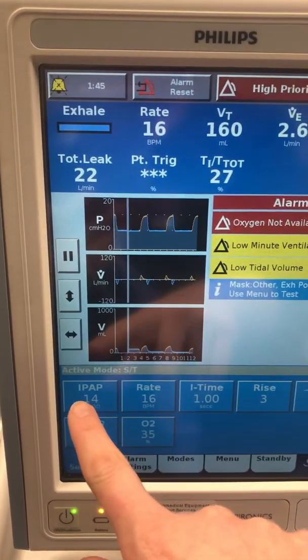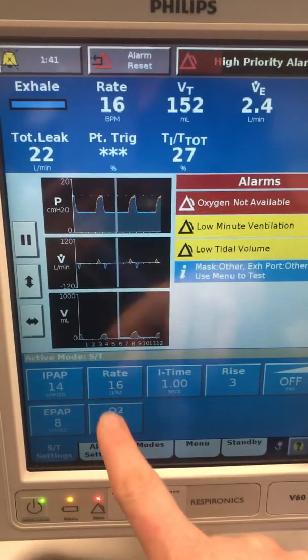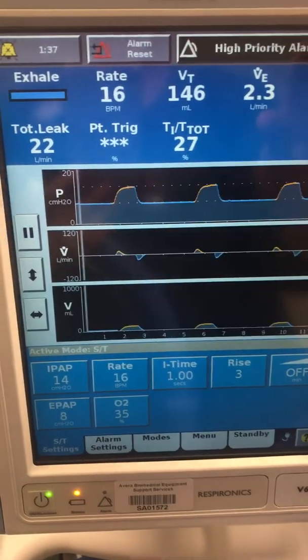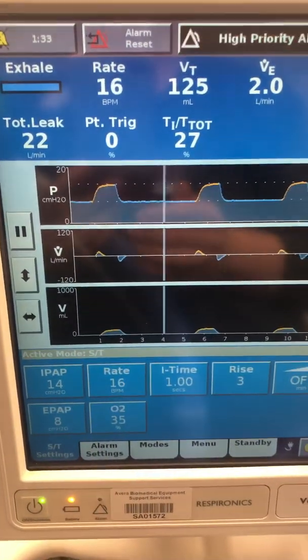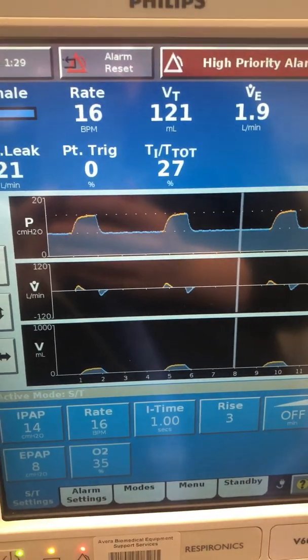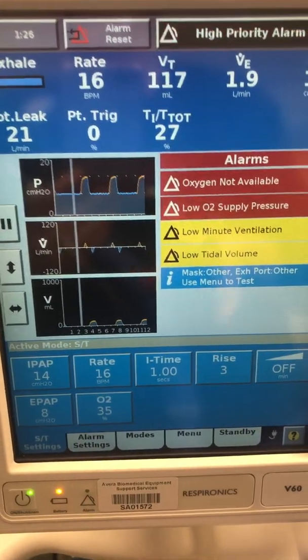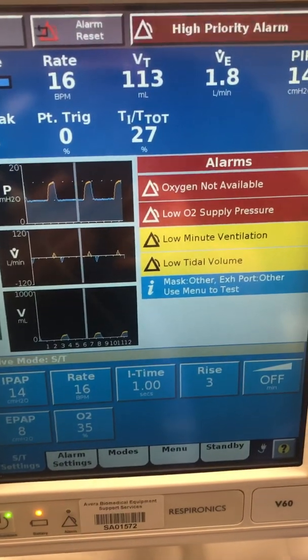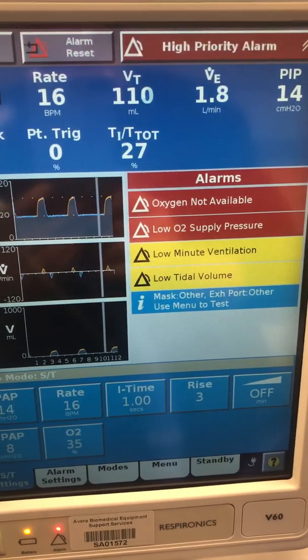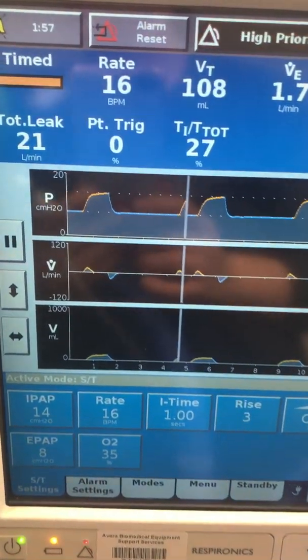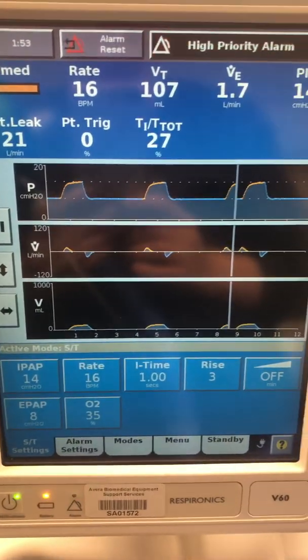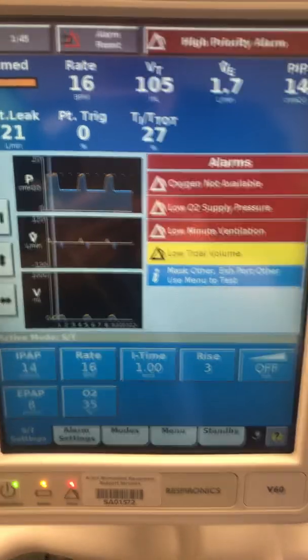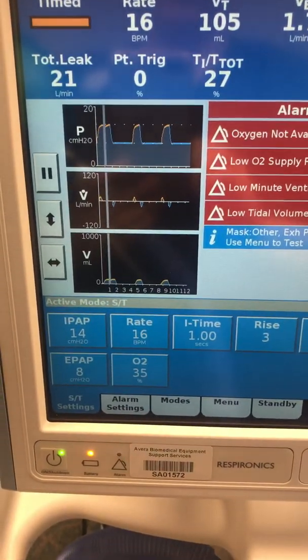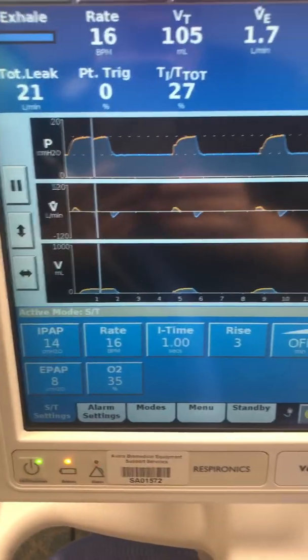Down here you can see the settings that you're allowed to change. You can change your IPAP, your respiratory rate, your inspiratory time, your rise time, your ramp time, and then your EPAP and your oxygen. Your IPAP is usually from 6 to 20 centimeters of water. For your respiratory rate, you want 8 to 12, or 8 to 20, or 12 to 20. Inspiratory time can be 0.8 to 1.2 seconds. Then you have the ramp time, which is how fast your patient's going to get to IPAP. That's based on their comfort. Your EPAP is usually 4 to 15 centimeters of water pressure, and you want to make sure that you have a pressure support between your IPAP and EPAP of at least 4. You can also set the FiO2 anywhere between room air at 21% and 100% oxygen.